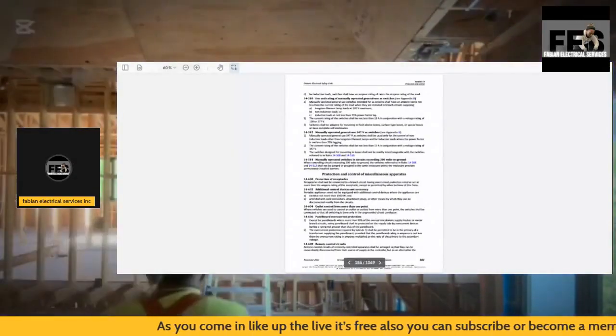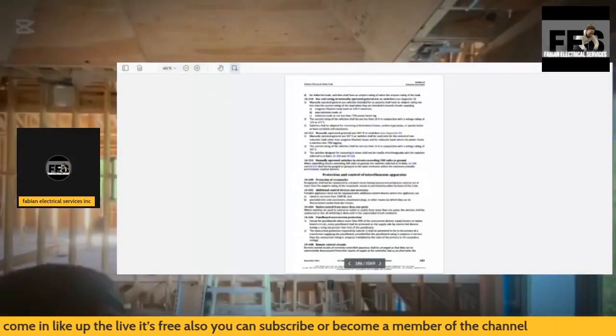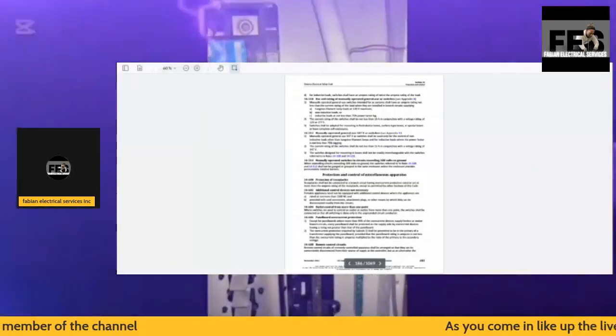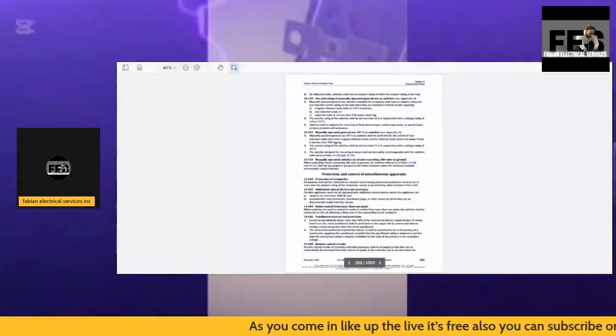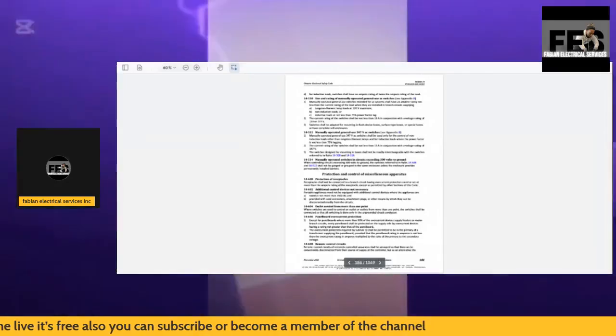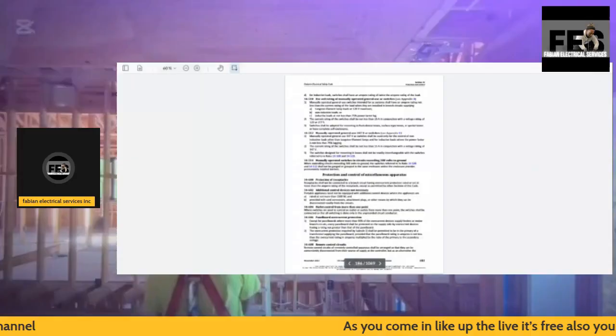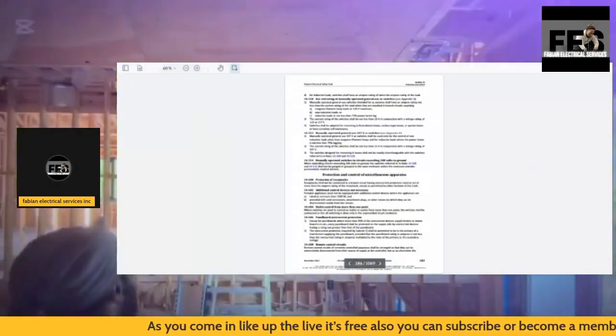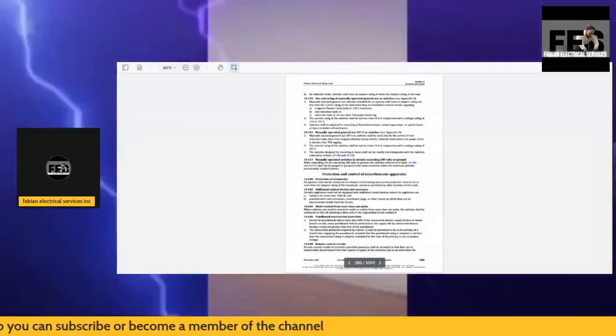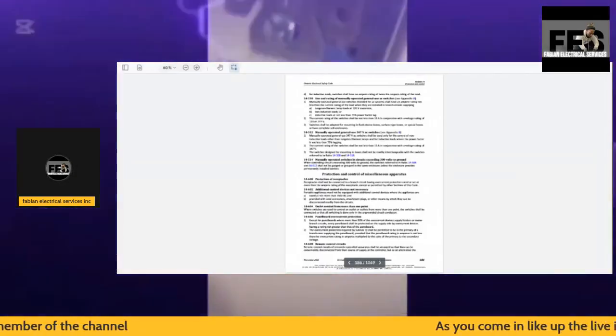So again, if you take a look at the bottom, it's going to say 14-606, and that is another rule that we have to look out for. It's a panel board rule, and it's a location rule, 14-606, and it basically says except for panel boards where more than 90% of the overcurrent devices supply feeders or motor branch circuits, every panel board shall be protected on the supply side by an overcurrent device having a rating not greater than that of the panel board.